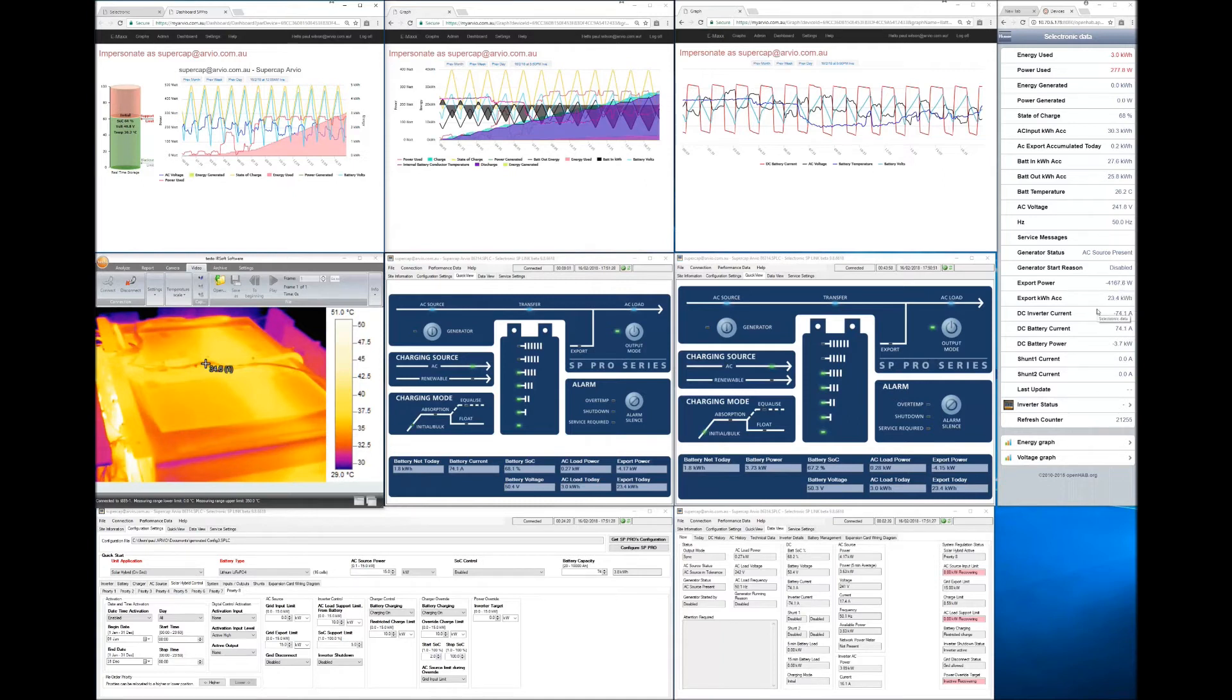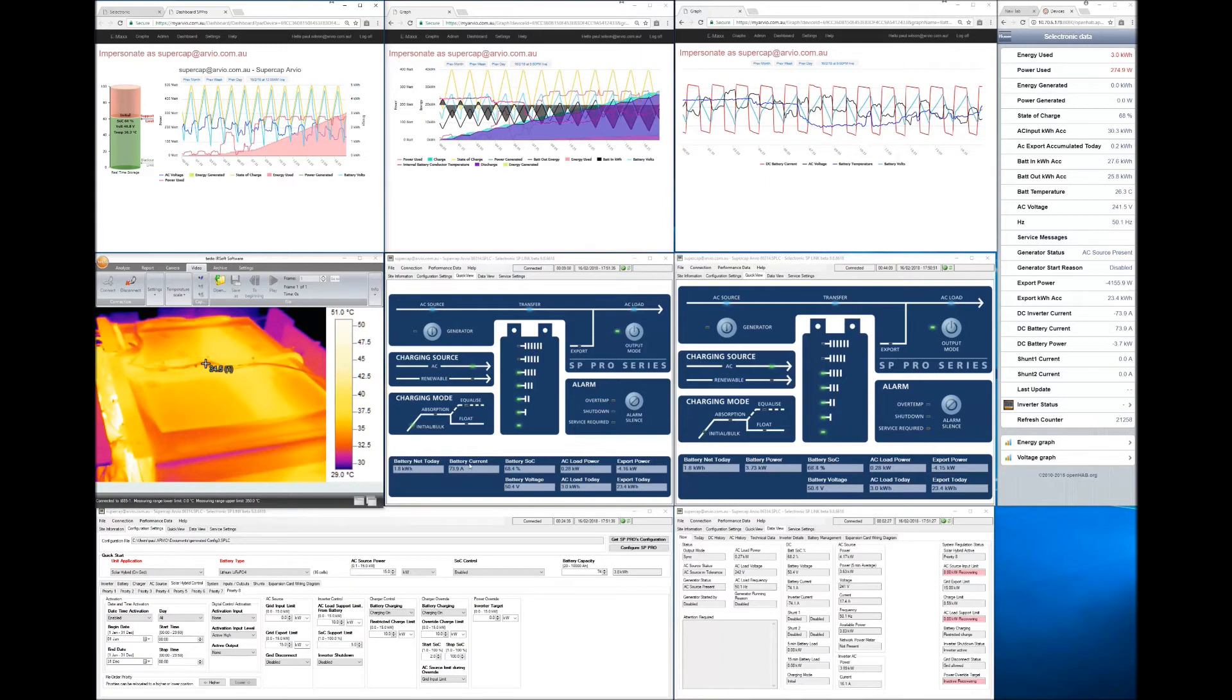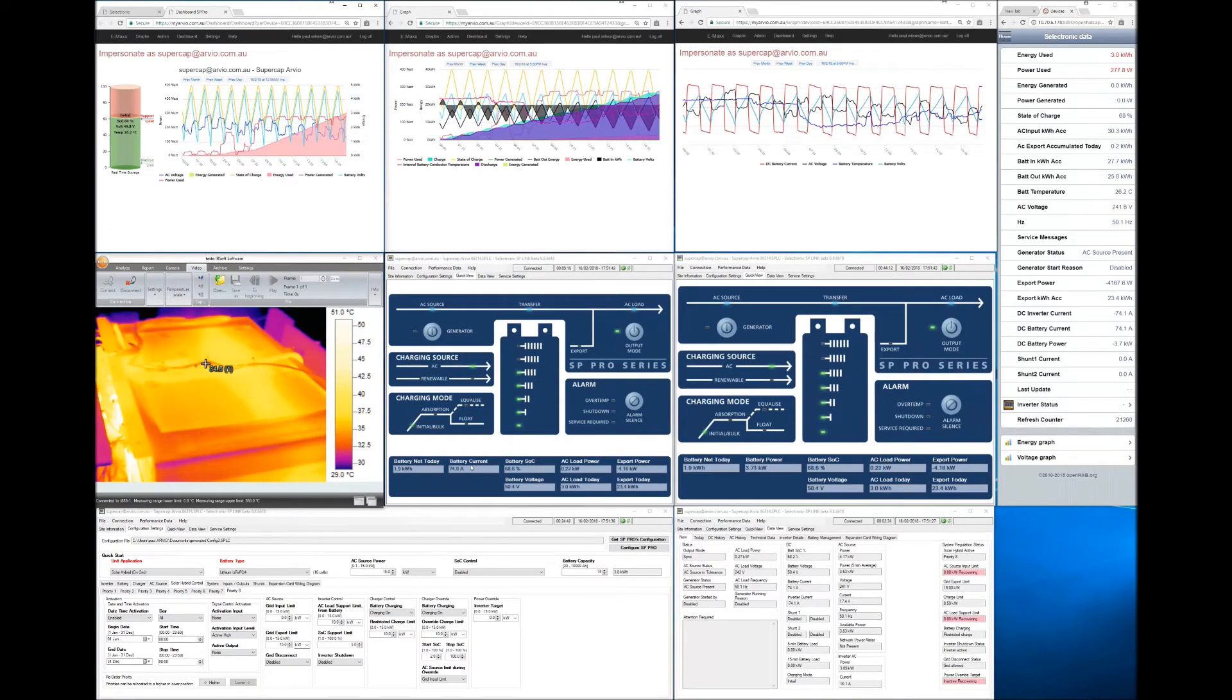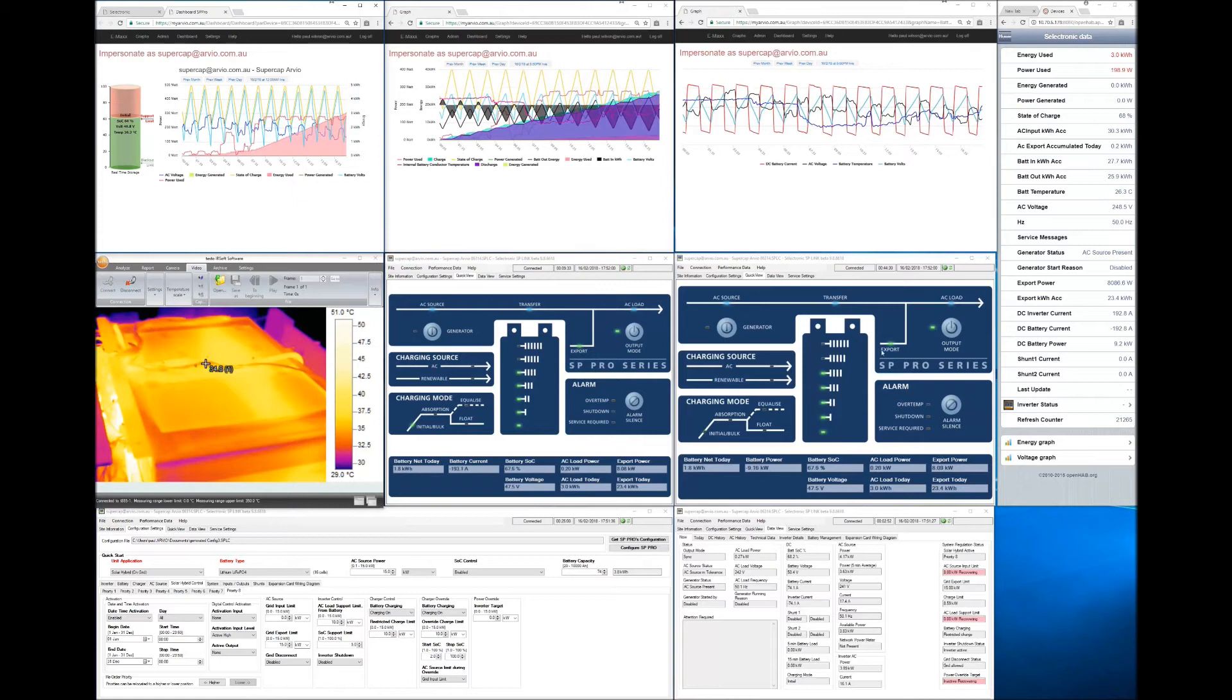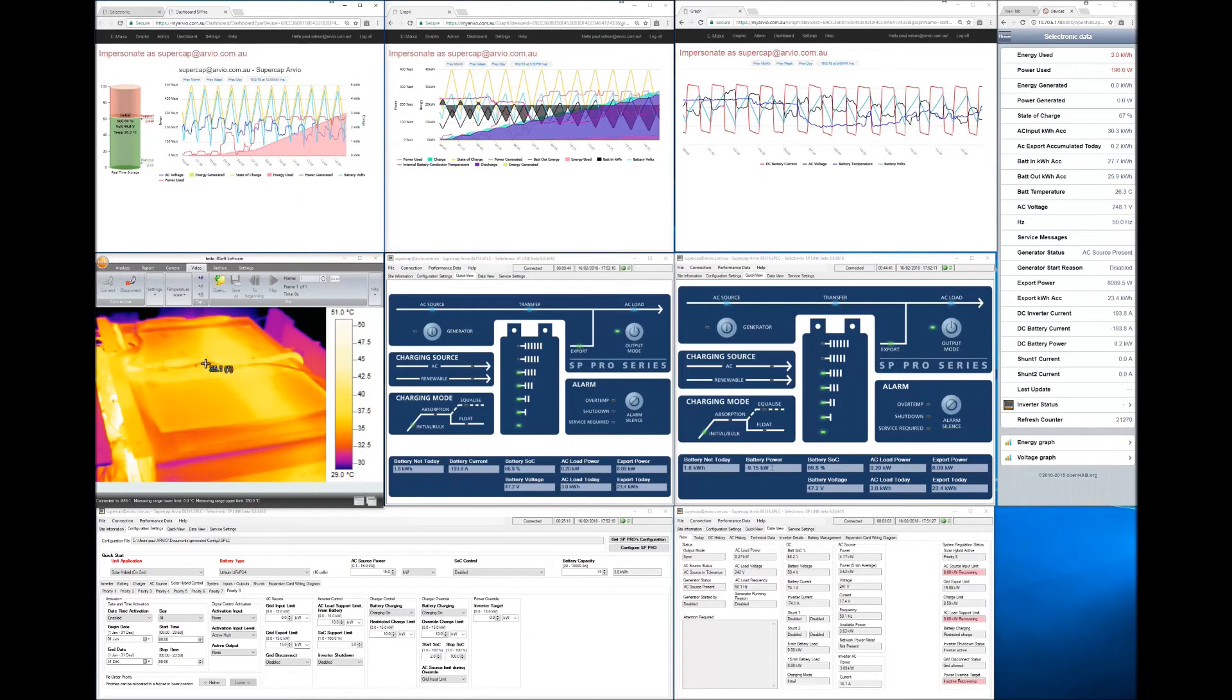And Yossi if I could just get you to turn it around now and get it to export back to the grid again rather than charge. Now in a moment you'll see the battery current here reverse because we are going to be exporting our supercapacitor battery energy into the inverter where it converts to AC. And we are now running at maximum export power so it's 190 amps. And the battery voltage fell obviously because it's starting to load the supercapacitor down. And we are now exporting the little green light over here we're exporting back to the grid. So we're exporting at 9.16 kilowatts. Now this is a 3.55 kilowatt hour supercapacitor exporting at 9.15 kilowatts which is almost a 20 minute discharge into the grid.